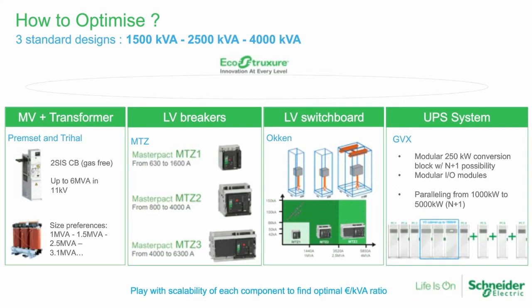And according to those different modes of operation, we need to have a continuity of the protection coordination of the whole system. So when we speak about protection coordination, it's really about having this secure end-to-end coordination between the medium voltage and transformer down to the distribution to the rack inside the IT room.